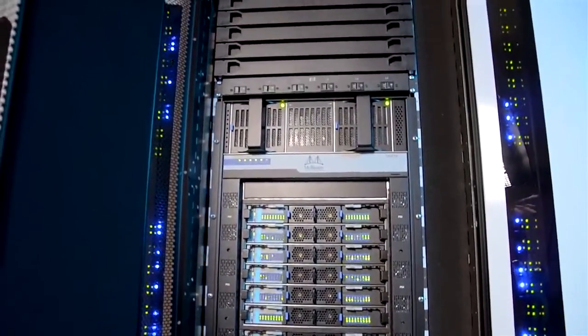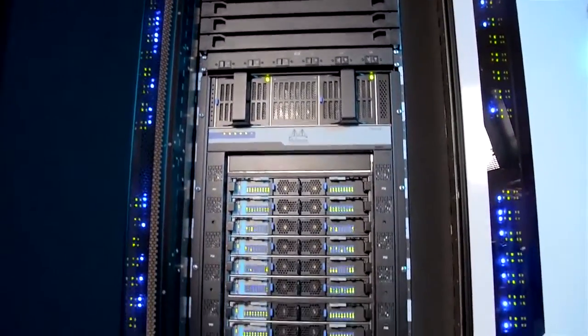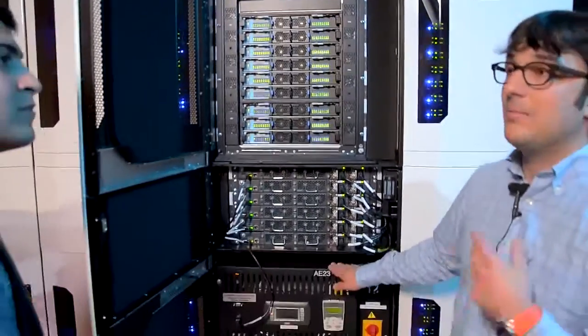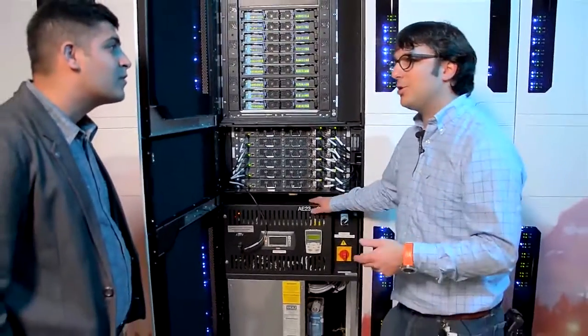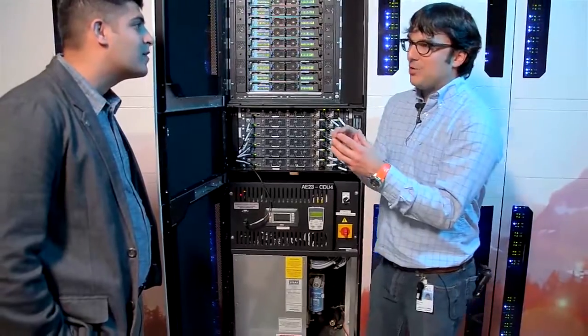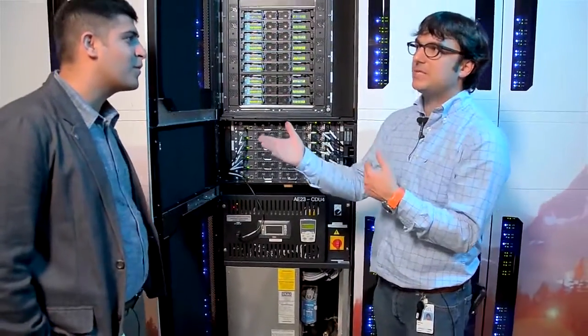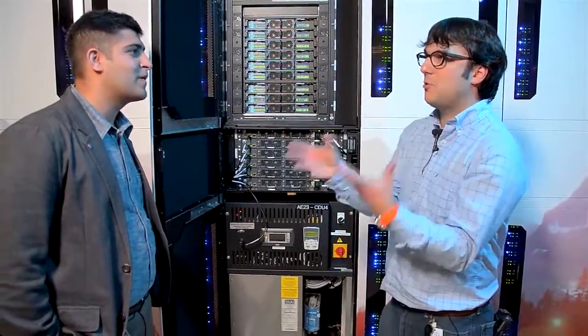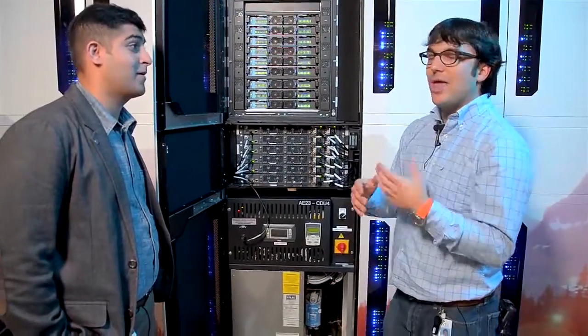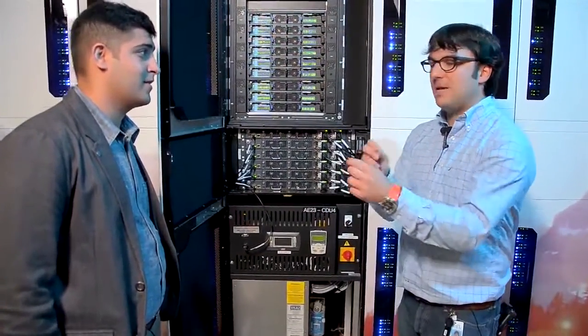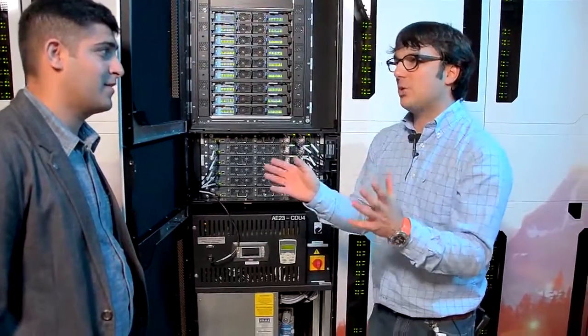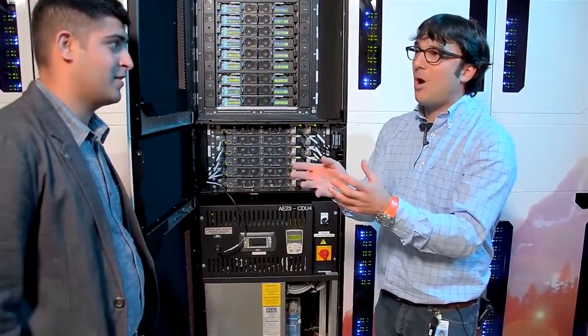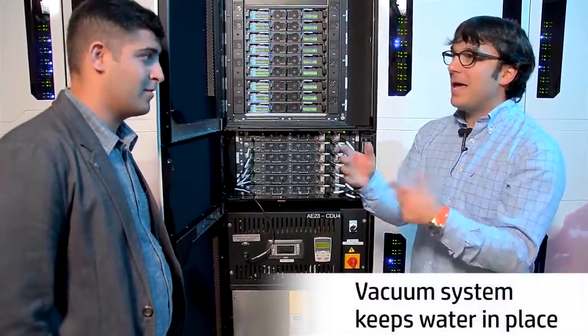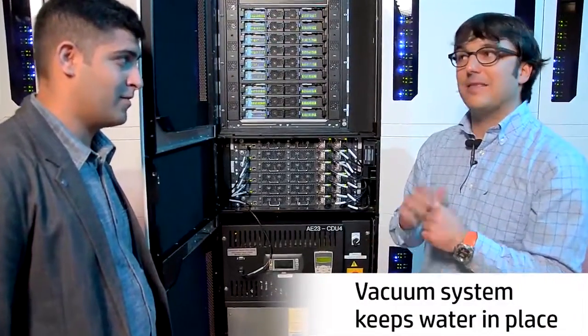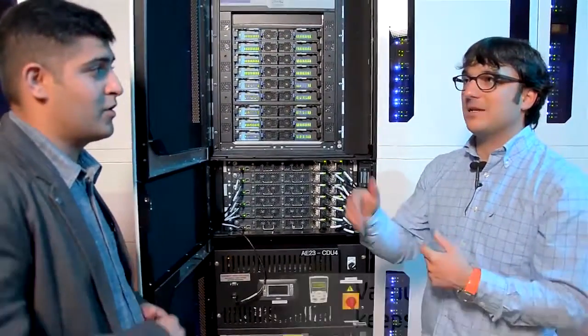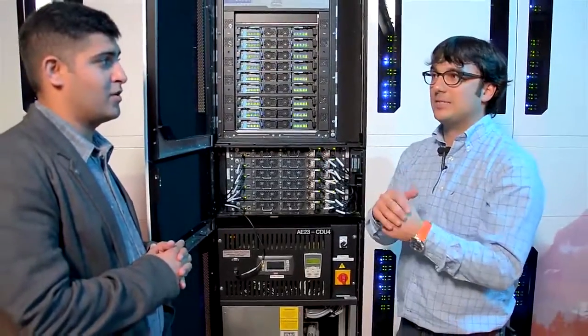The key aspect here is that not only does it have a positive displacement pump, it also has a vacuum pump. Why do you care? Well, by having a vacuum pump, it means we're running the secondary side—the water that flows through the racks—out of a vacuum. So if any pipe were to come loose for whatever reason, instead of dropping water we'd be sucking in air, and we can automatically detect it very fast with a bubbler and alarm that there might be a leak somewhere.